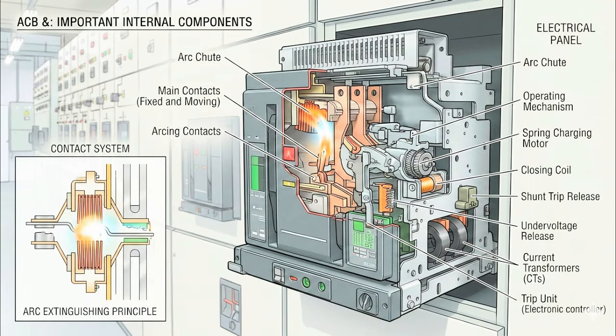Now let us understand the important parts of an air circuit breaker. The main contacts carry the normal load current. These contacts must be clean and in good condition for proper current flow. The second part is the arc chute. The arc chute helps to extinguish the electrical arc during the switching operation. It improves safety and protects the breaker from damage.